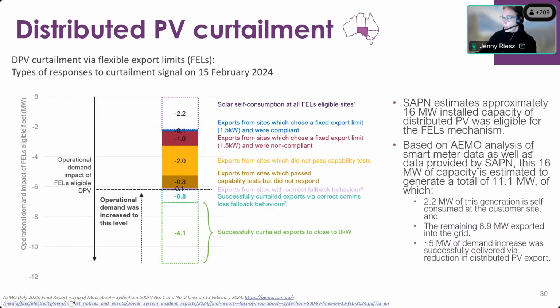And based on our analysis of smart meter data, we believe that 16 megawatts was generating a total of about 11 megawatts in these periods. About 2.2 megawatts of that was self-consuming at the customer site. The remaining 8.9 megawatts exported into the grid. And we believe about 5 megawatts of curtailment was successfully achieved during this period to bring demand up from about 11 megawatts back up to the 6 megawatt mark or so in that event.